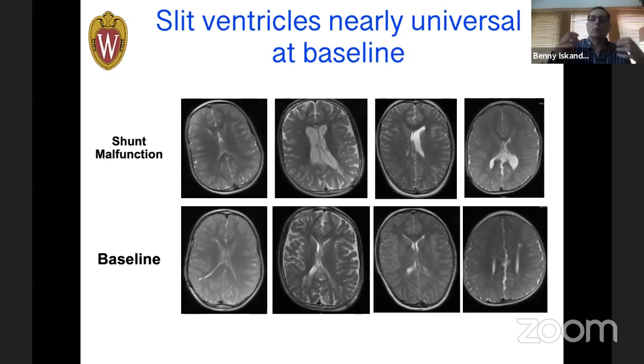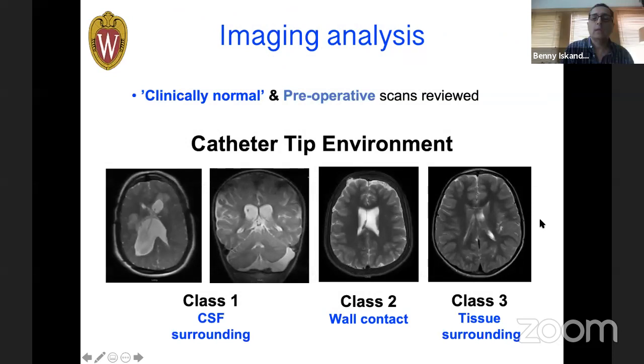And then we took it one step further and decided to look at the tip of the catheter. The tip of the catheter in this case, for example, is sitting inside the ventricle, surrounded by spinal fluid, whereas this one is attached to ependyma, and this one is completely enclosed in ependymal tissue. So these class 1 CSF catheters, as we call them, the tip is surrounded by CSF. We have not had any one of these fail. All of the failures were in class 2 and class 3, which tells you that you don't have to have very small ventricles for the shunt to fail. All you have to have is small ventricles around the tip of the catheter.